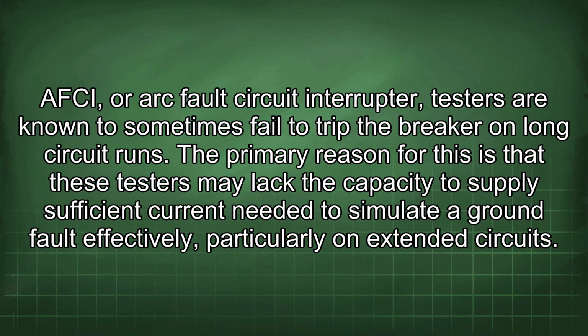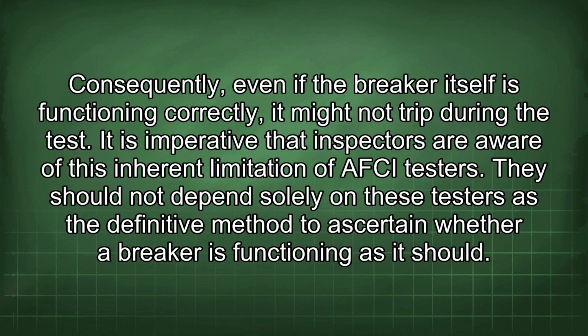AFCI, or arc fault circuit interrupter, testers are known to sometimes fail to trip the breaker on long circuit runs. The primary reason for this is that these testers may lack the capacity to supply sufficient current needed to simulate a ground fault effectively, particularly on extended circuits. Consequently, even if the breaker itself is functioning correctly, it might not trip during the test.